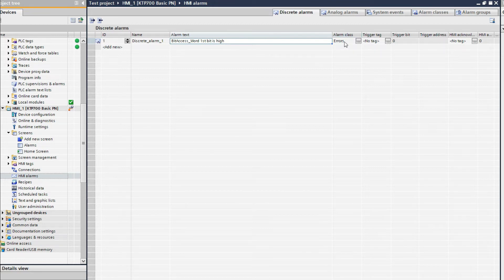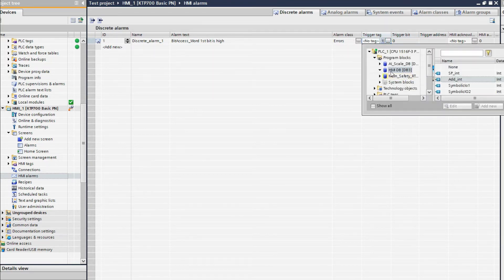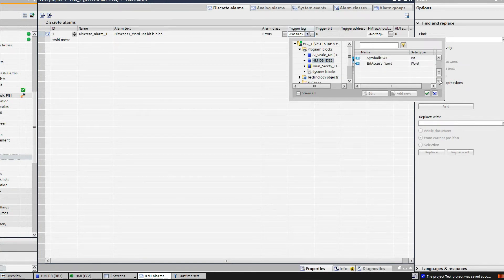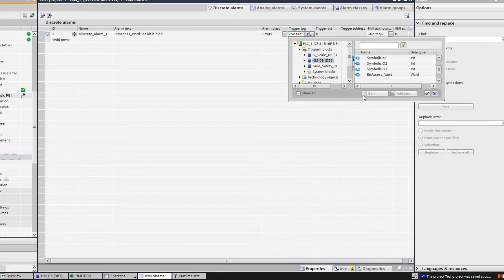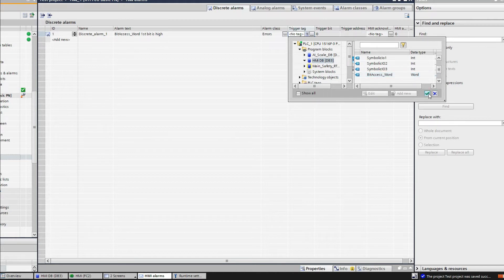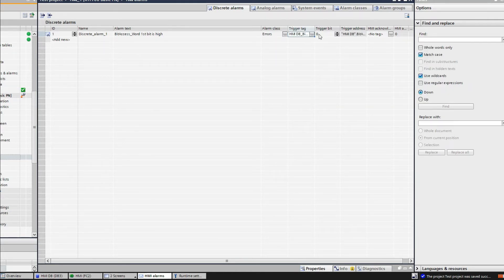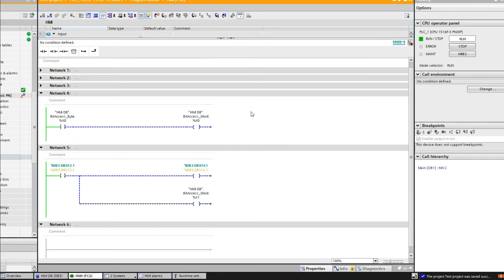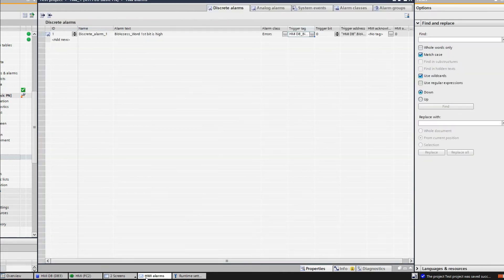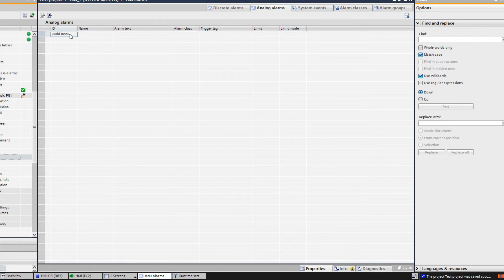The alarm class is zero. For the trigger tag number, if you go to HMI DB you can see it only shows integer or word tags — meaning for HMI tags you have to choose a word tag; you cannot use a binary tag here. But from a word tag you can create discrete alarms because a word has 16 bits, so for each individual bit you can create an individual alarm. I will use bit access word and trigger bit zero.